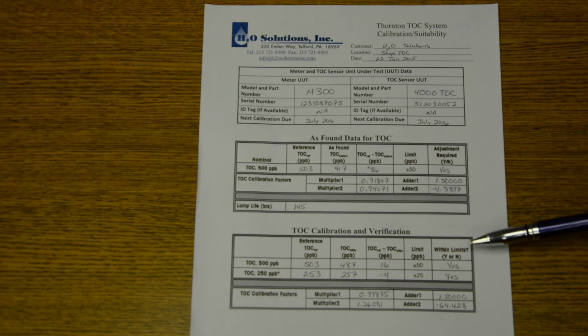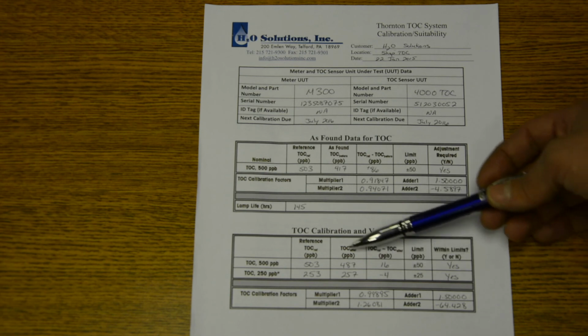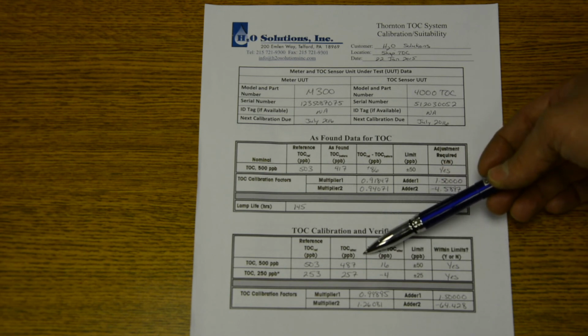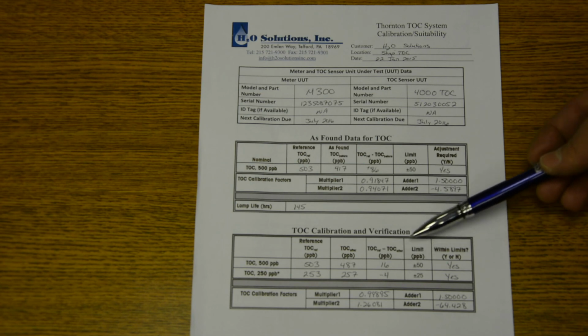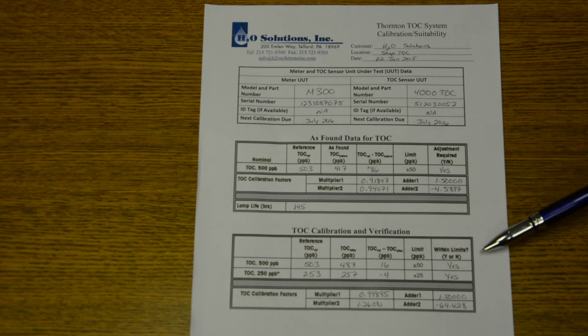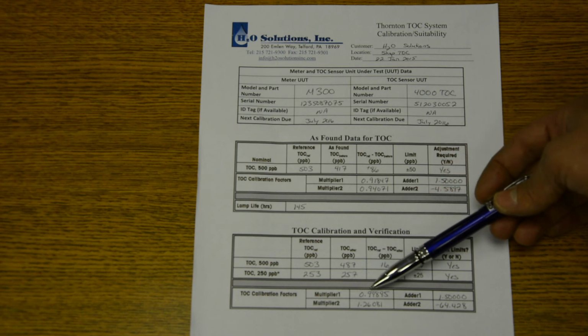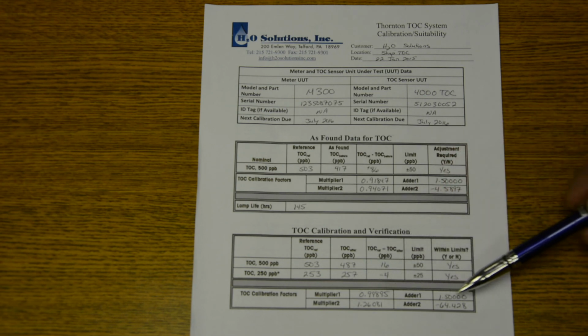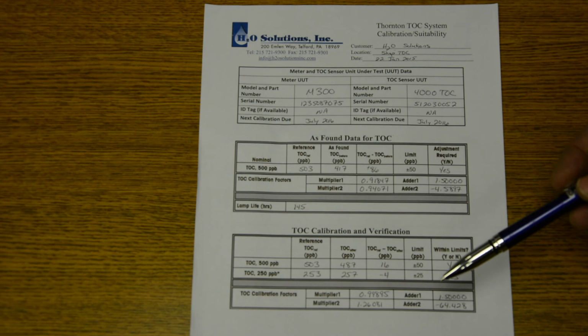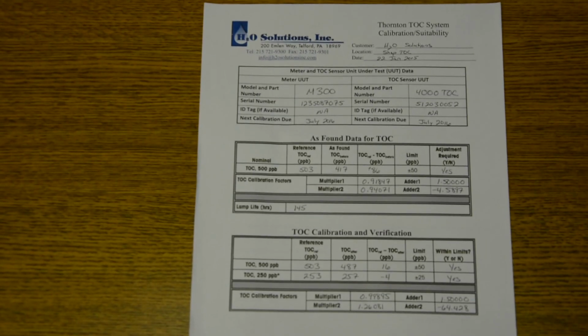On the bottom, this is your actual calibration. This is your solution that you started with. This is what it was reading after the calibration, and then this is the difference between that and whether it was within limits. If it was within limits, we write yes on both sides here, and the calibration passed. If not, then the calibration was not successful. Then you write down the TOC calibration factors after the calibration, and you're writing down your multipliers and adders on the end of this page. That page is for the calibration.